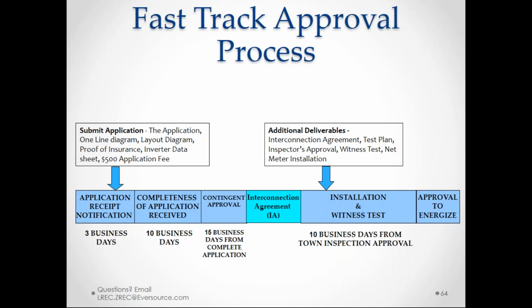Once we issue the interconnection agreement, those documents outline what you have to do: customer signing, returning them, returning payment for witness tests if applicable, returning test procedures if applicable, or if it's under 100, returning a certificate of compliance. As usual, you get town inspection approval and the subsequent meter change, and once all items are met, we issue the approval to energize.